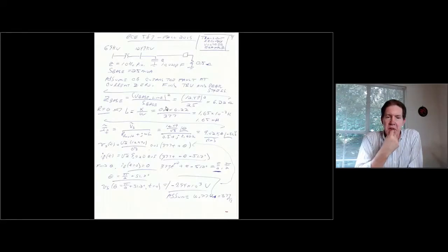So now we're going to take a look at a worked example. And this is going to be a little bit more complicated than the simple formulation that I did in the theory part of the lecture. I wanted to add some things to it and just show you if I add fault resistance, and also substation resistance, how that's going to change the nature of the solution.